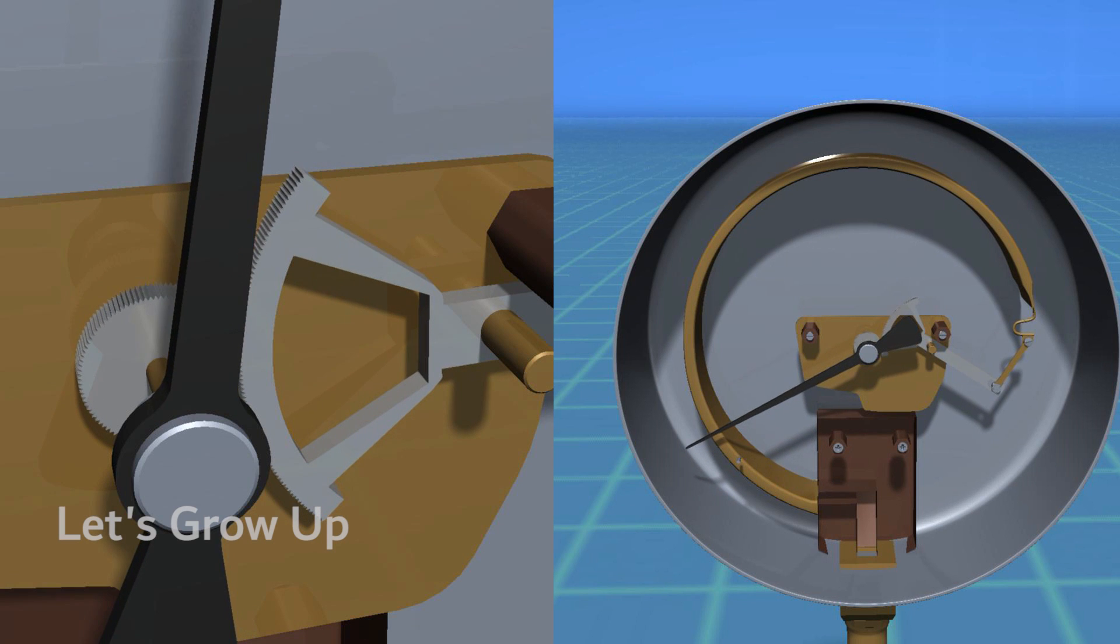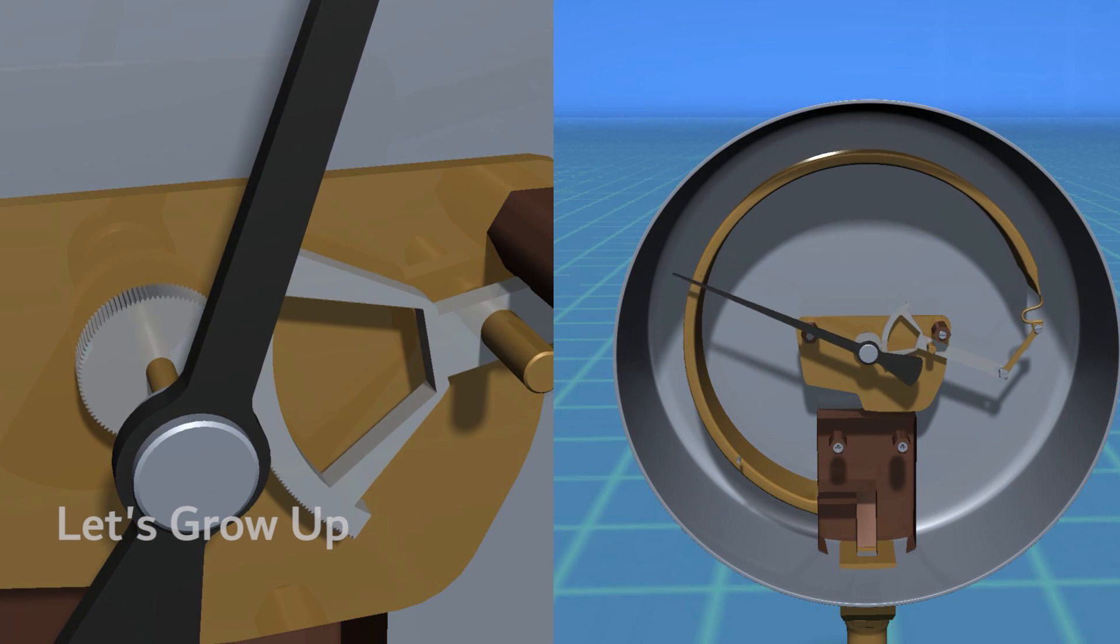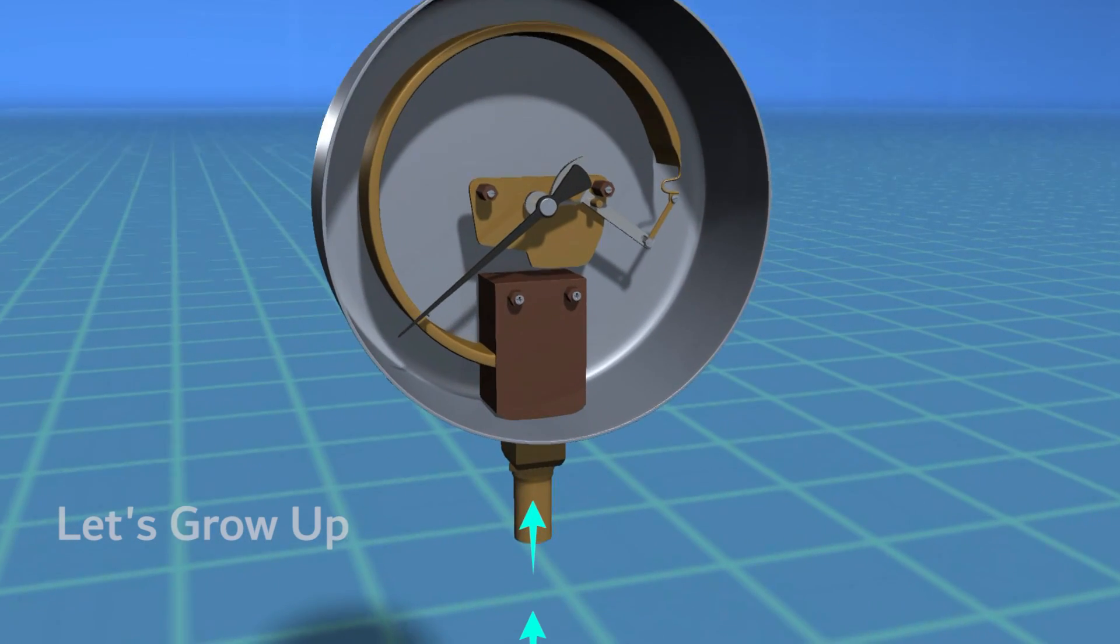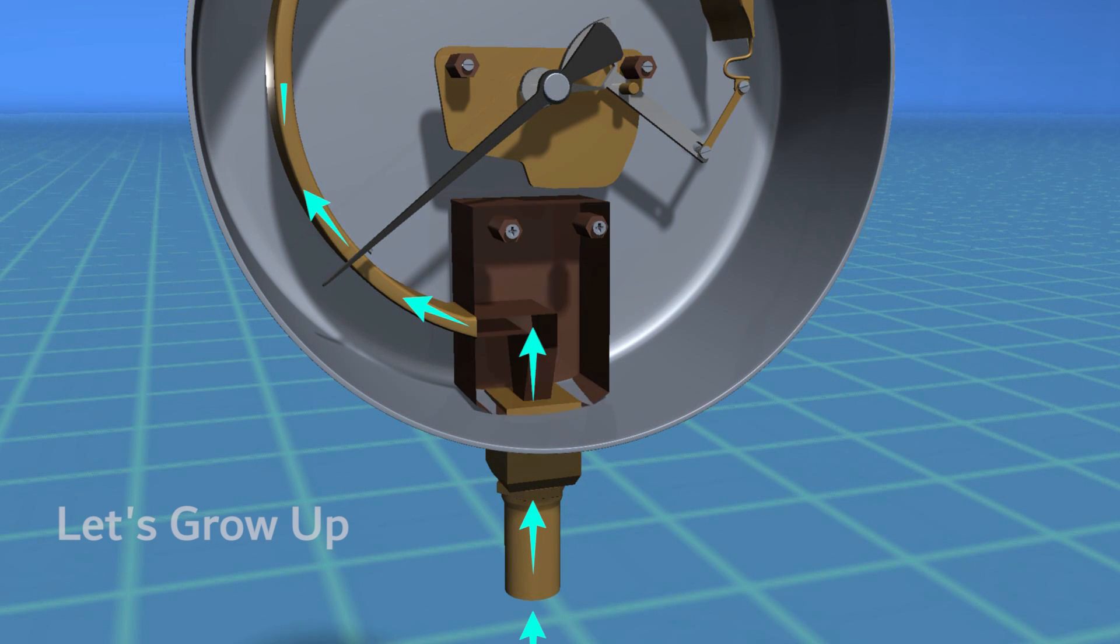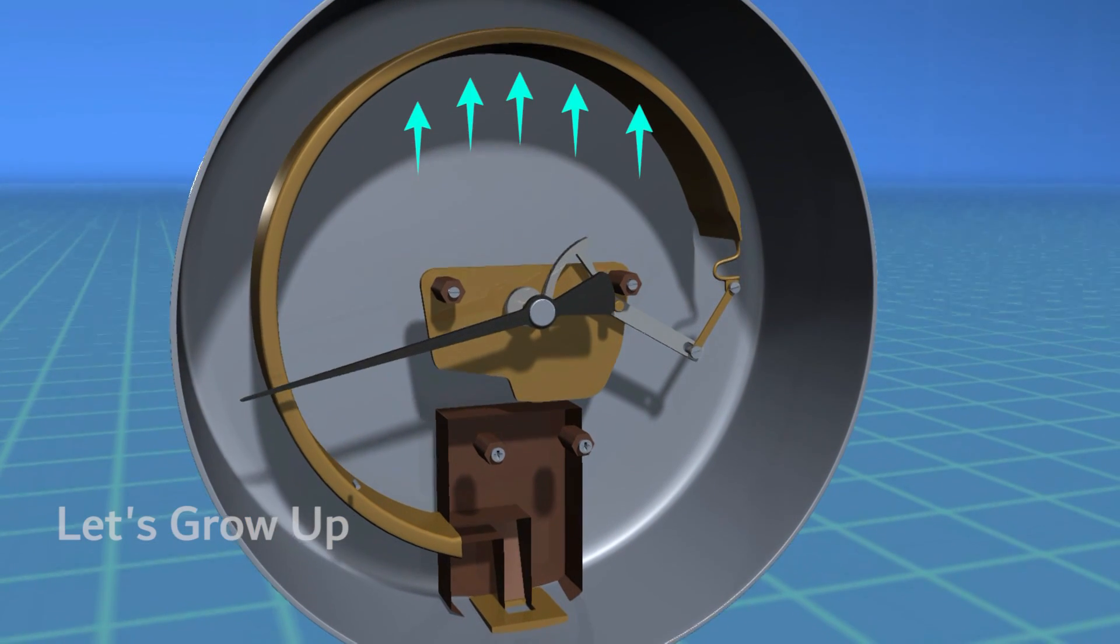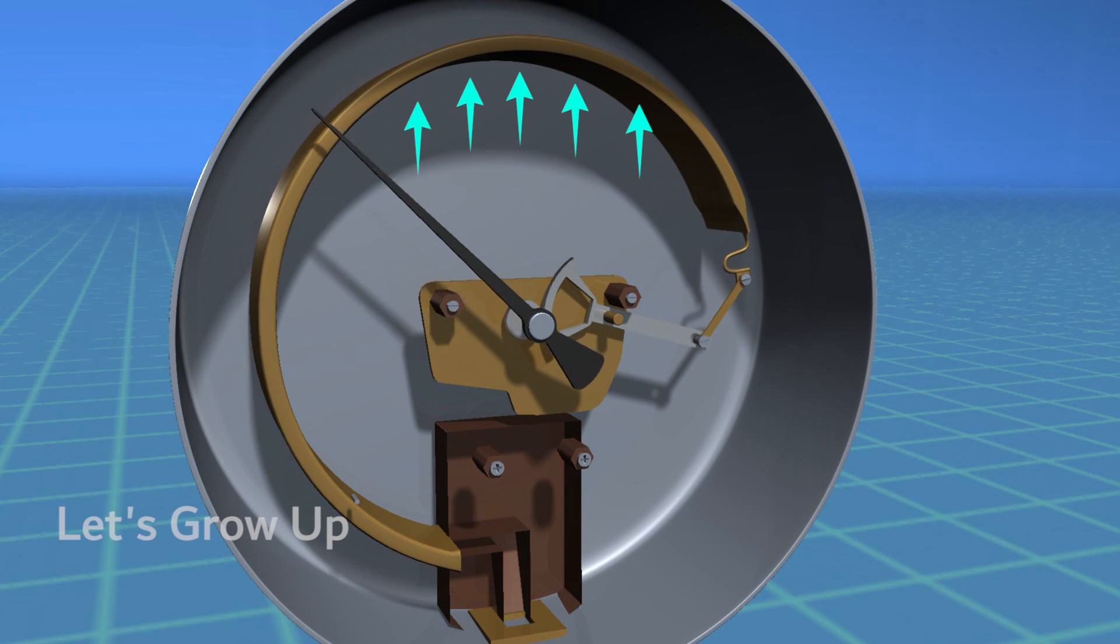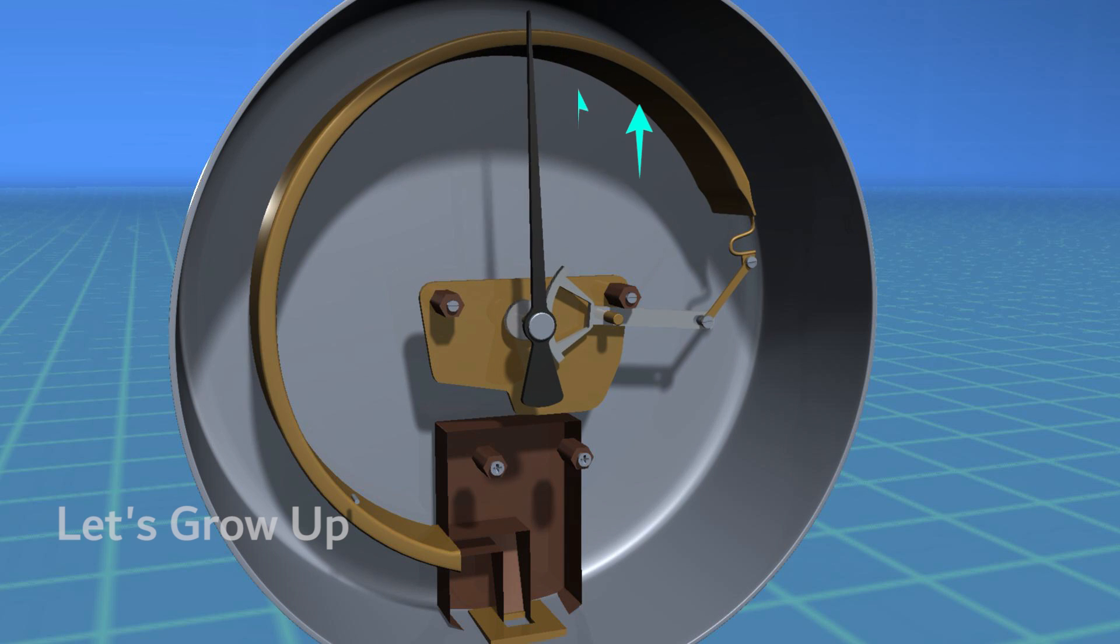Let's see how it works. When air pressure is applied to the inside of the Bourdon tube, it causes the tube to straighten or elongate. This change in shape is proportional to the pressure exerted on the inside of the tube.